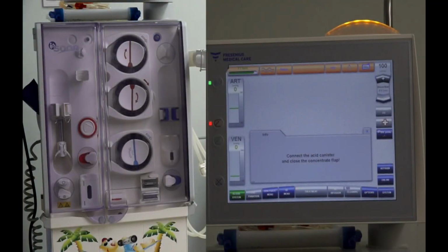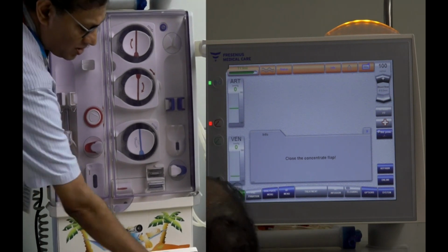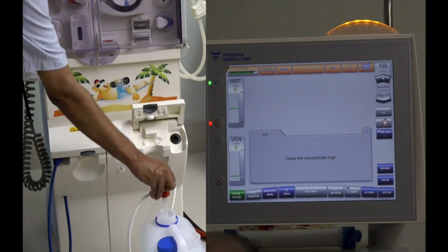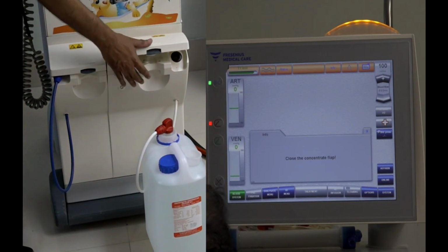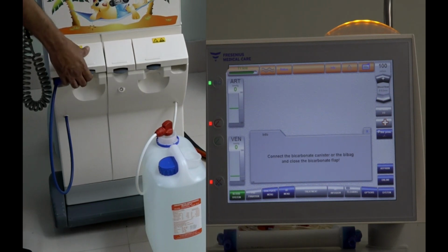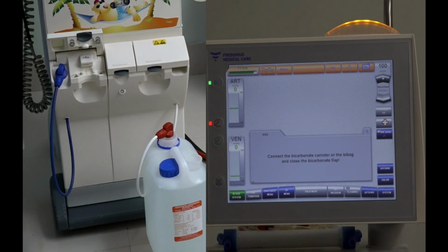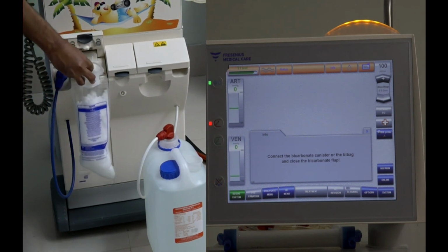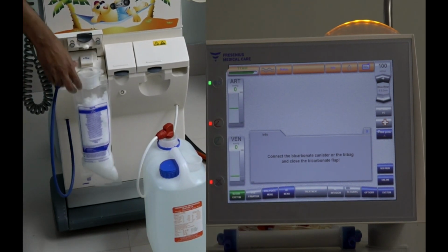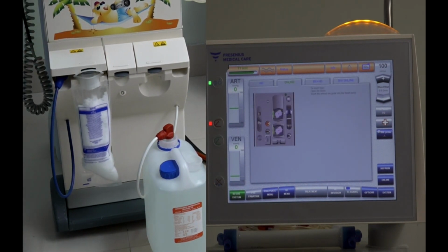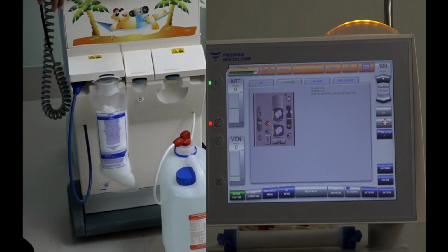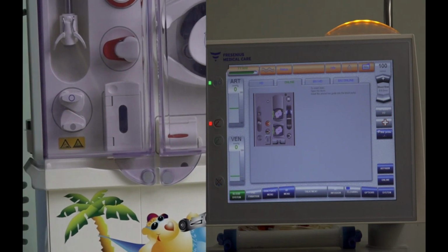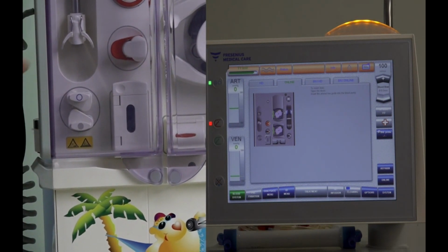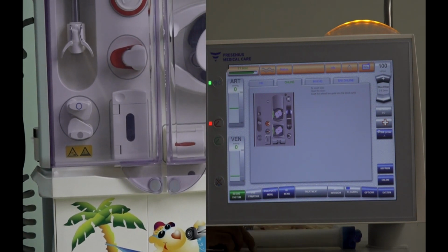In order to prepare the dialysate, the machine is now asking us to connect the acid concentrate. The acid concentrate is a liquid concentrate as with conventional hemodialysis. So we place the concentrate stick in the container and close the flap, and now the machine is asking us to connect the bicarbonate concentrate, which is a sterile powder in this case. So I will place the bibag here and close the concentrate flap. Once this is done, the machine is in a self-test where it is going to test all the alarms and the monitoring systems, and it is also now allowing us to start the loading of the blood lines.